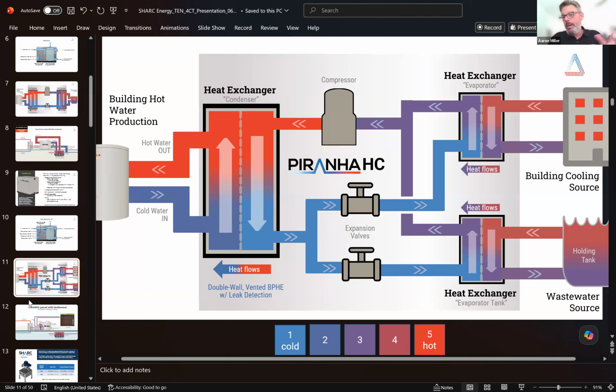hot water production. So imagine this is happening right now in a building in Brooklyn. They've got geothermal. It's an all-electric building. In fact, I'll talk about it a little bit later, Alafia. They've got a geothermal loop providing condenser water to all the apartments in the building. Heat pumps are doing heating and cooling. And it also feeds our hot water heat pump. And then there's also a sanitary tank that's dug under the parking deck for the building. So when the Piranha turns on for hot water, it looks at two thermistors. It looks at the tank and the loop.